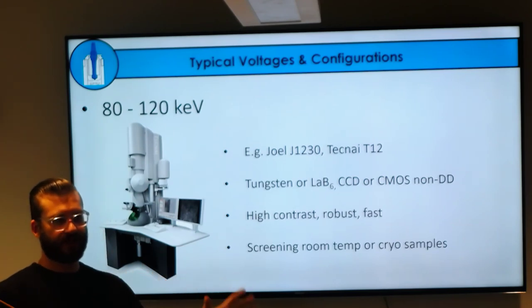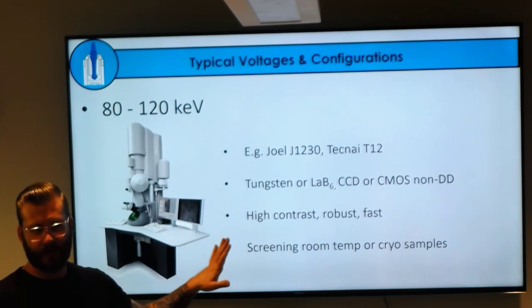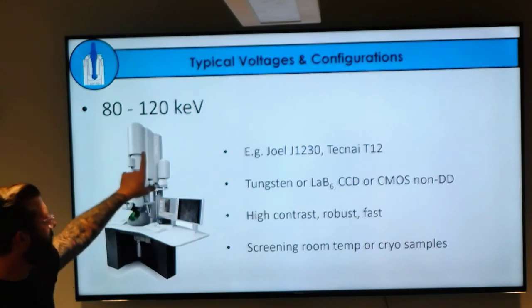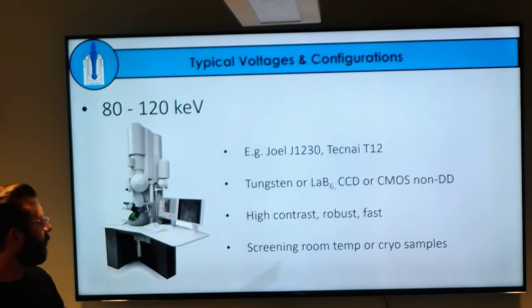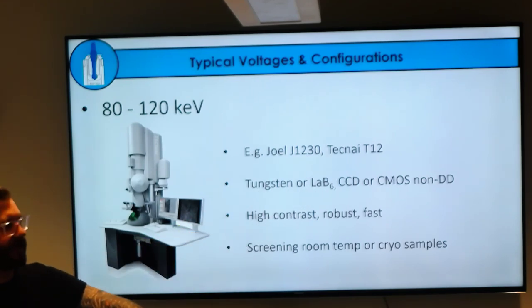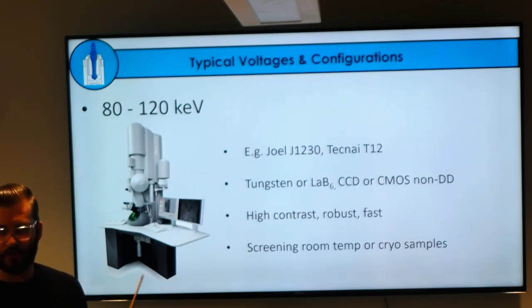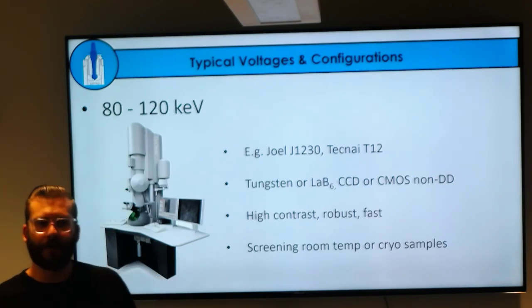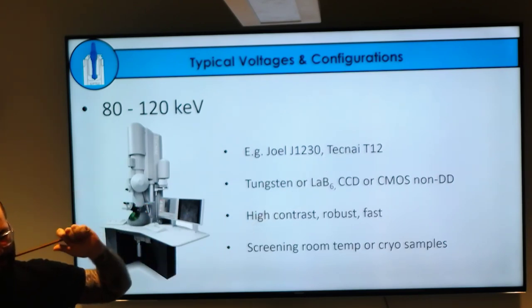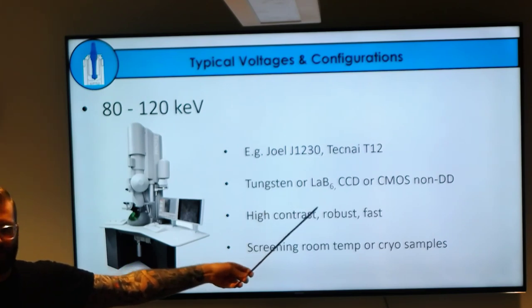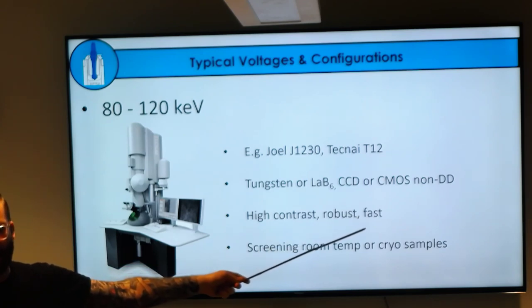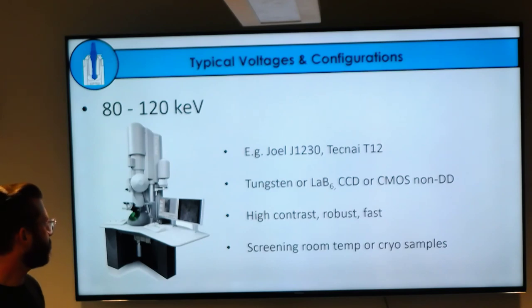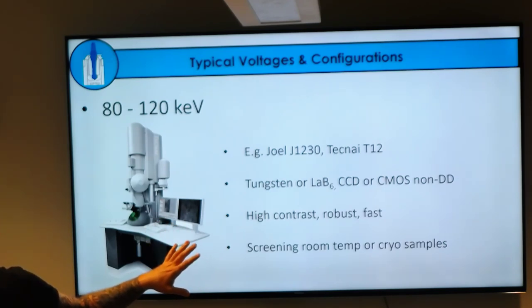I'm going to go over some standard configurations you might see. On the low end, the 80 to 120 keV range: we have a Jeol 1230, our small screening microscope down by the NMR magnets, at 80 keV, and a Tecnai T12 which is being relocated. These both have filaments—either tungsten or LaB6—and usually don't have direct detectors; they use CCD or CMOS chips. The nice thing is they're cheap, fast, robust, and usually high contrast. Good screening microscopes for biological samples.